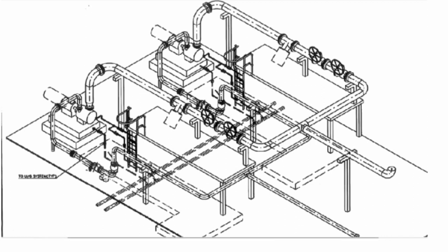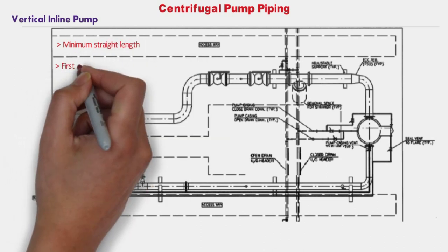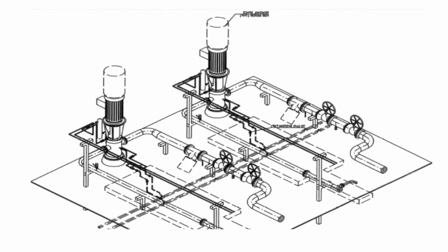For vertical inline pumps, the plan view shows the piping arrangement. Minimum straight length requirement as per the pump vendor must be provided. The first support close to the pump nozzle shall be decided to satisfy requirements for free end sagging, and the stress engineer should review. The isometric view for this pump type is also shown.